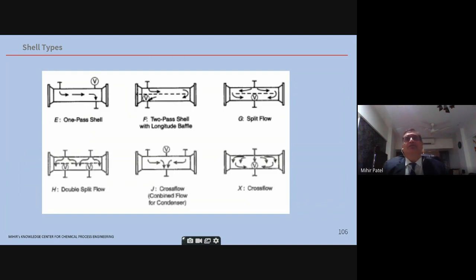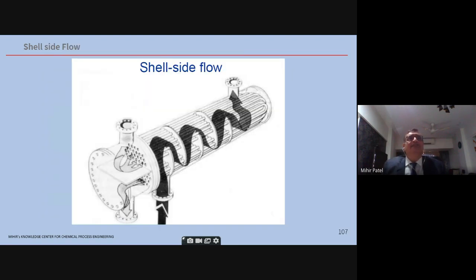X type is the cross flow type. In X type, you have the lowest pressure drops. So we had used X type, for example, in a SRU plant, sulfur recovery unit, for the reheaters before the converters. So the pressure drop was very less. And the X type, basically, is not a long exchanger, it is a box type exchanger. Because you don't have much play on the flow going through, it becomes a box type exchanger. And the kettle type, not shown here, but the kettle type reboiler has a phase separation integral to the exchanger. So we'll see it in the reboilers as we go forward. Shell side flow is shown, as one can see, just for information. So it's a horizontal baffle. The shell side flow is going, and the tube side flow is also shown here. 2-pass exchanger on the tube side.